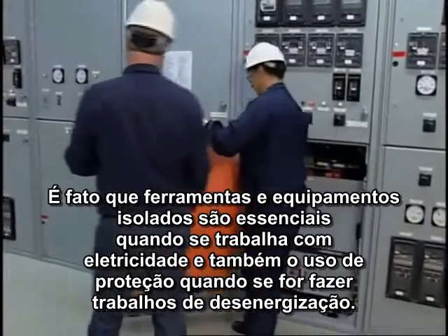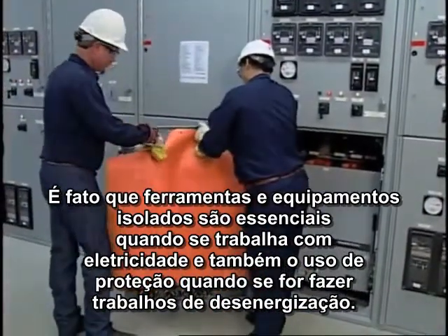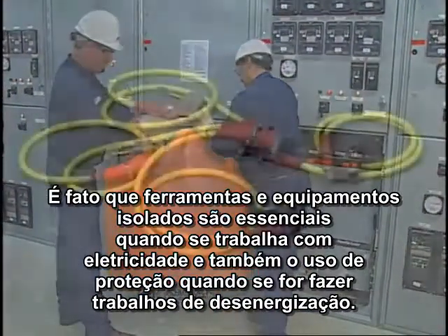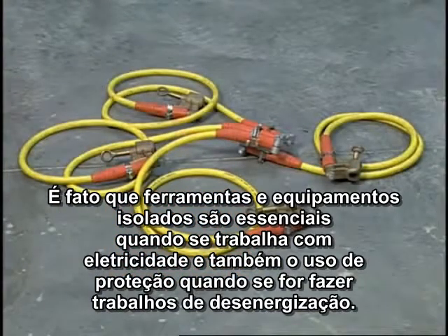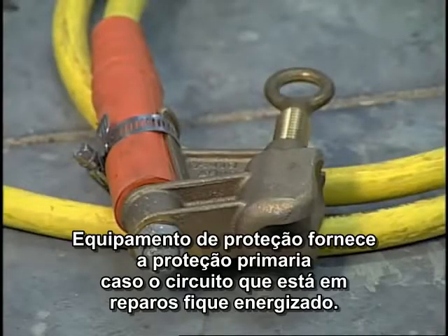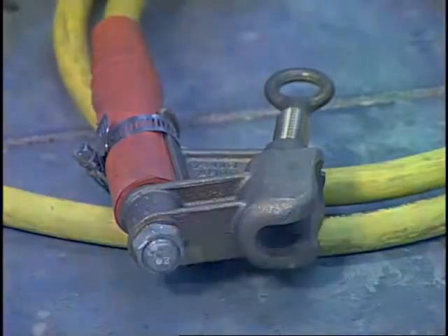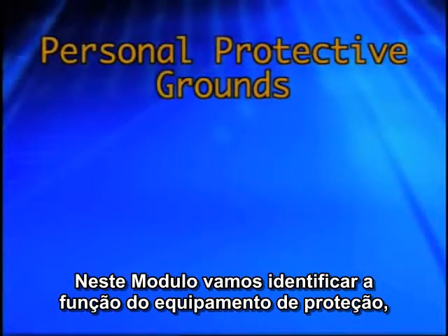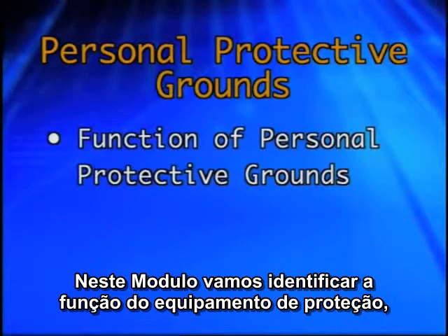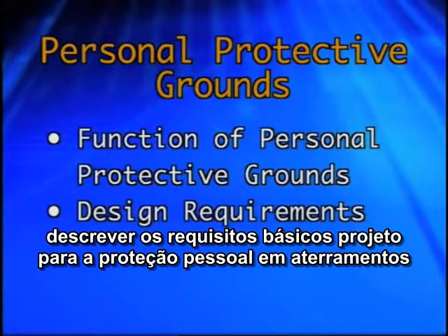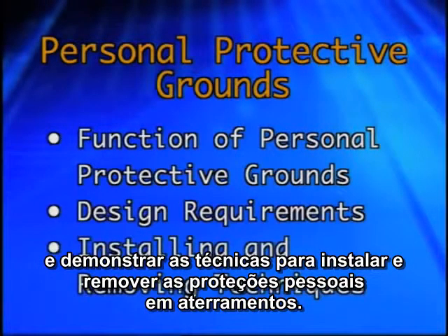It is well recognized that insulated tools and equipment are essential for doing energized work. It is just as essential to use personal protective grounds when doing de-energized work. Personal protective grounds provide the primary protection in the event a circuit under repair inadvertently becomes energized. In this program, we will identify the function of personal protective grounds, describe the basic design requirements for personal protective grounds, and demonstrate techniques for installing and removing personal protective grounds.